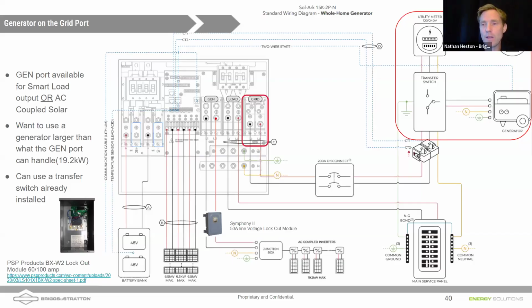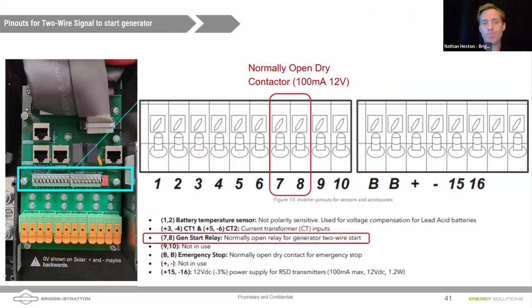Now, keep in mind that generator is not going to be running long, and it typically is only running when there's not enough solar to keep up with the loads. So it's not like you're losing a lot of solar. When that generator starts up, it starts up because the batteries are low and the AC coupled solar was not covering the home's loads and not charging the batteries.